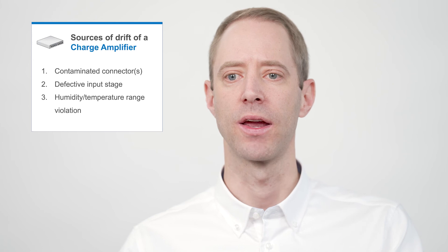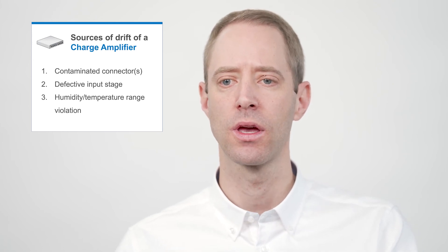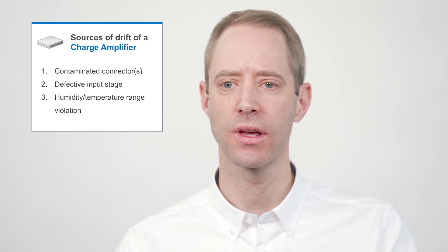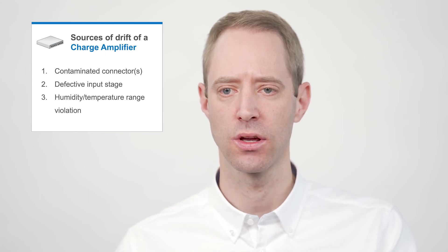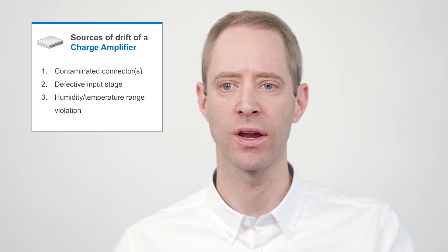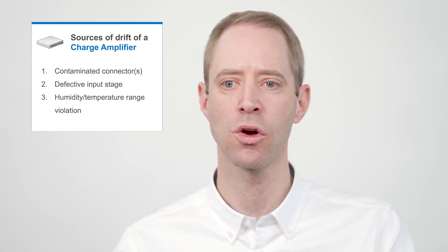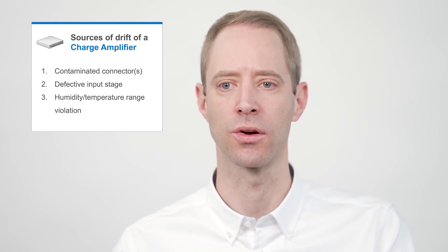Also with the charge amplifier, contamination of the connector can lead to drift. An additional source of drift is a defective input stage. In such a case, a leakage current at the charge amplifier input or an insufficient insulation of a charge amplifier circuit component can be the root cause.